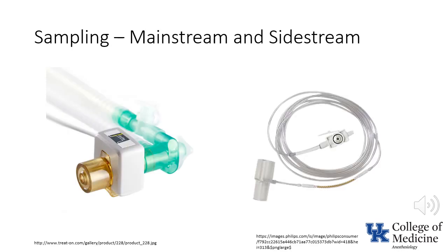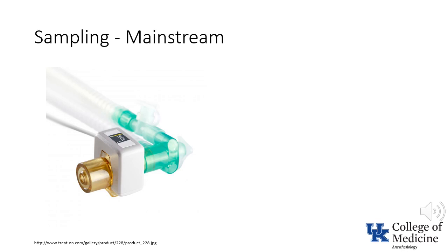There are two different ways to sample respiratory gas for the purposes of measuring exhaled carbon dioxide: mainstream and sidestream. With mainstream capnometry, the measurement is actually performed on gas which is in the anesthesia circuit.